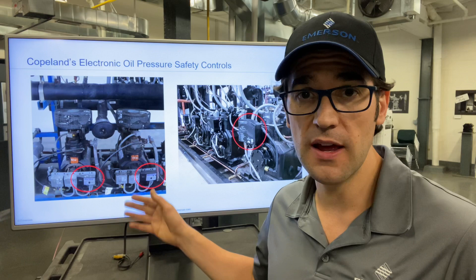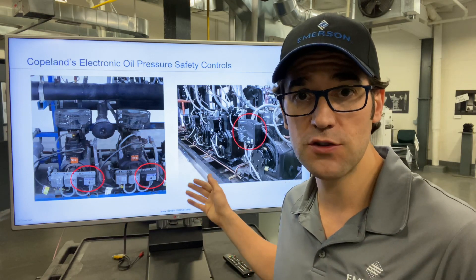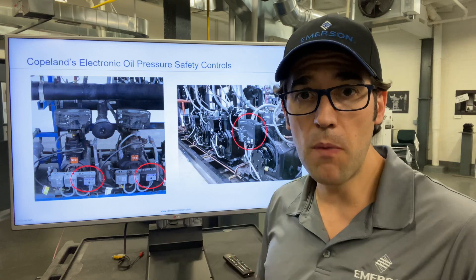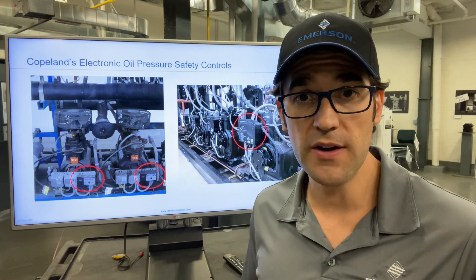You can see behind me here I have Sentronic and I have CoreSense, which are now Copeland compressor electronic modules, and they monitor oil pressure. It's an oil safety device to make sure oil is feeding all the bearings.